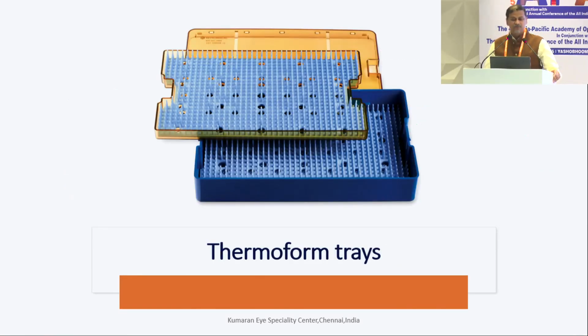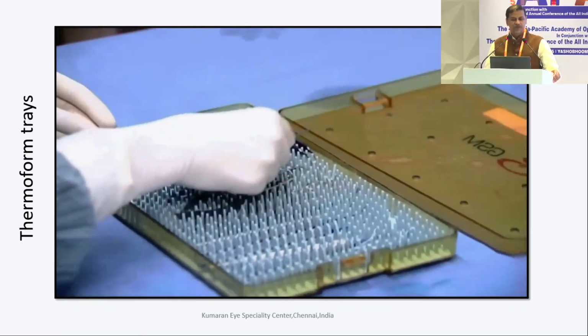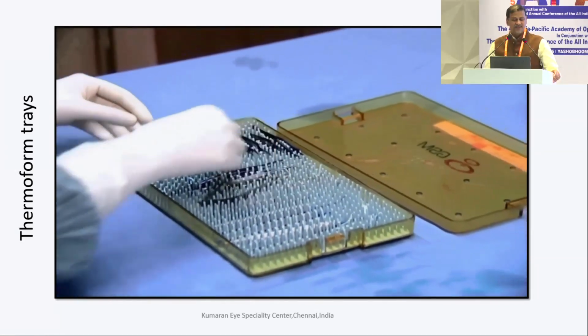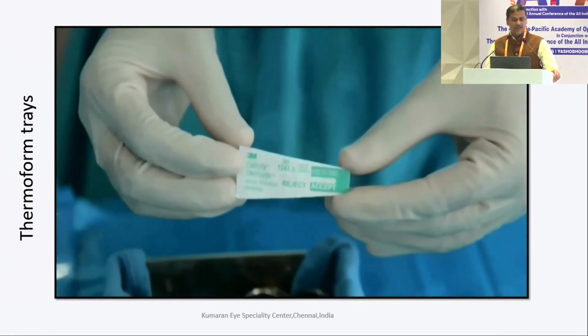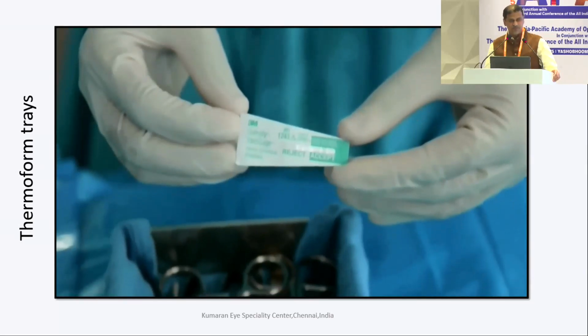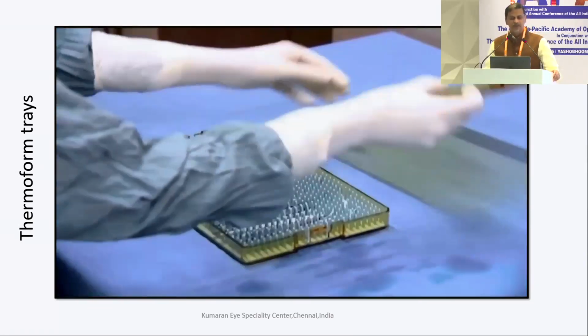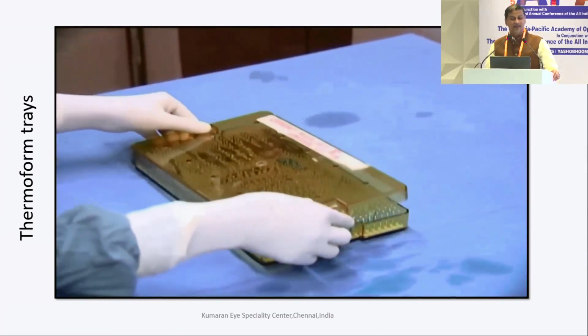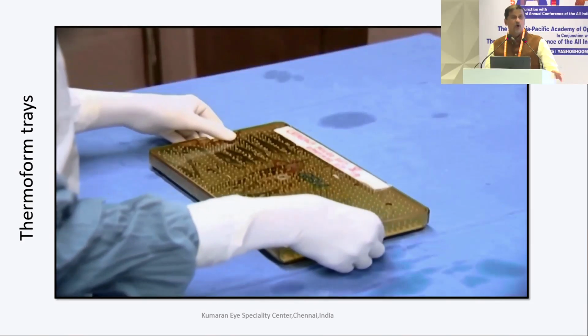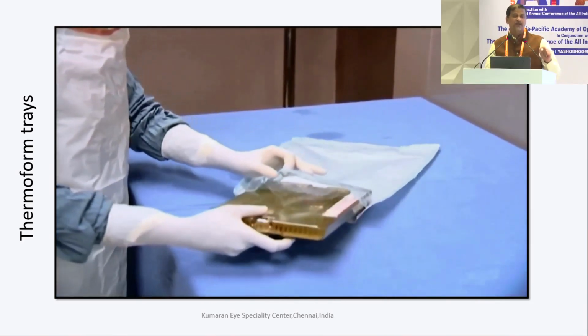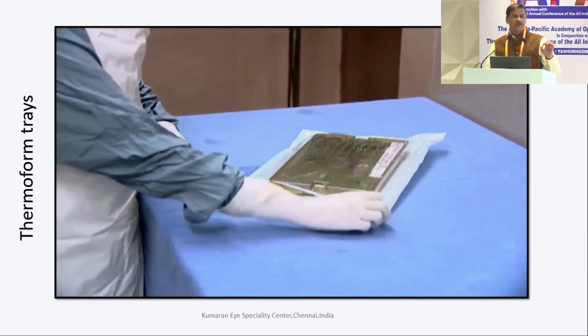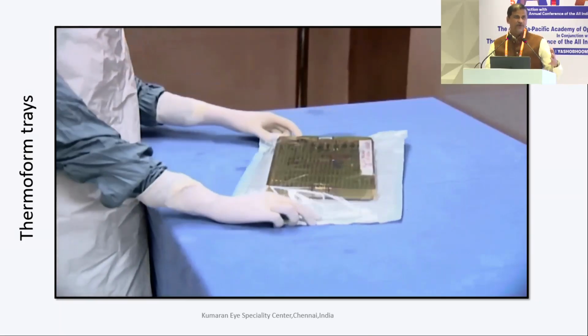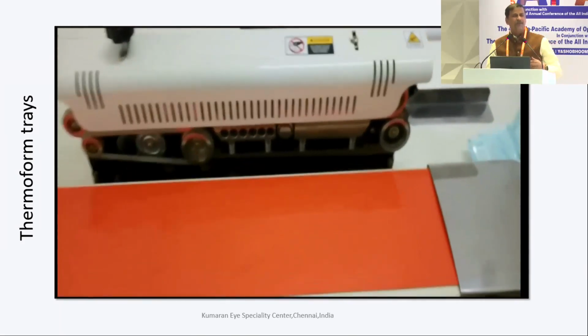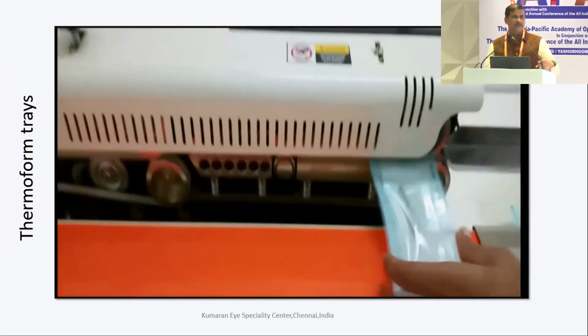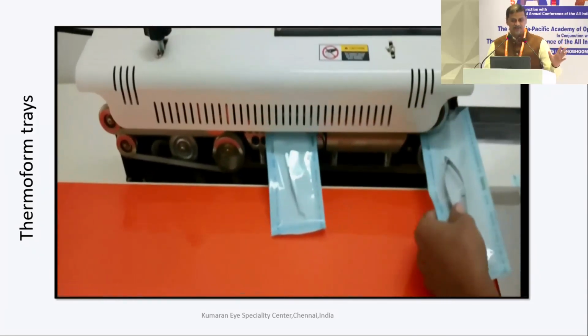Thermoform trays are very, very effective. The only thing you have to follow is to have adequate space. Don't pack these trays with a lot of instruments, because you need to allow steam to penetrate. Use a class 5 integrator in every tray. If you have 10 cases, always have 10 instrument sets and put a class 5 into each tray. Don't have a single tray and each time open it up and take these instruments for all 10 cases. It's always good to have 10 trays for 10 cases or so.